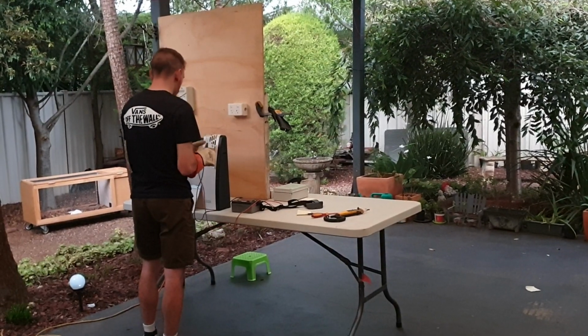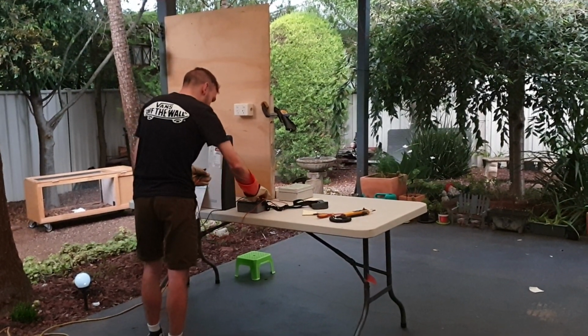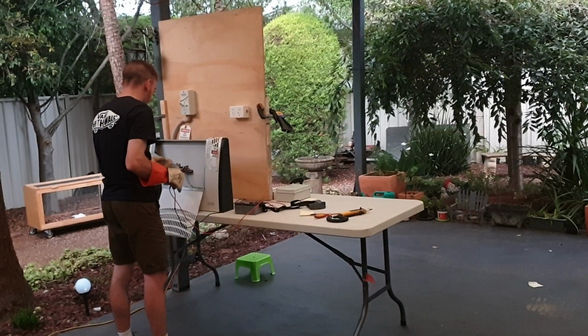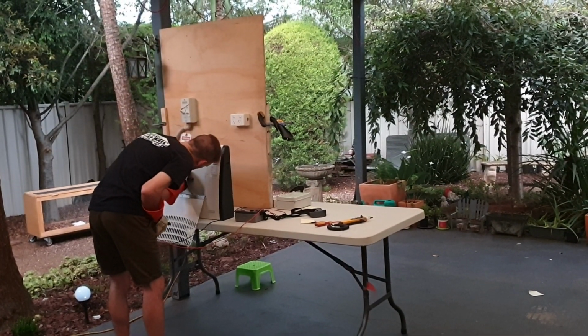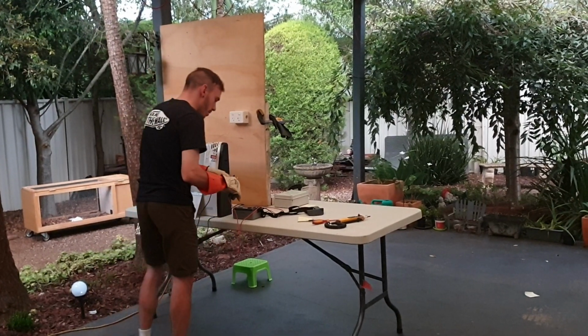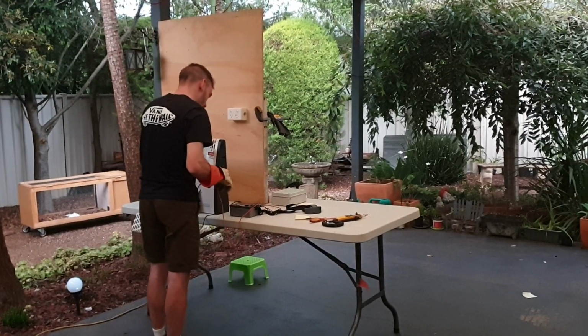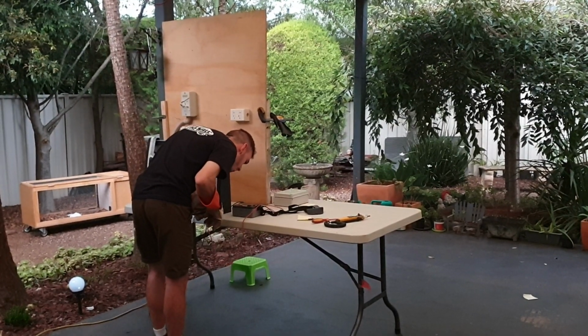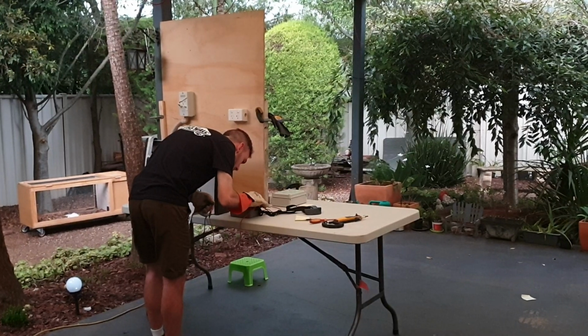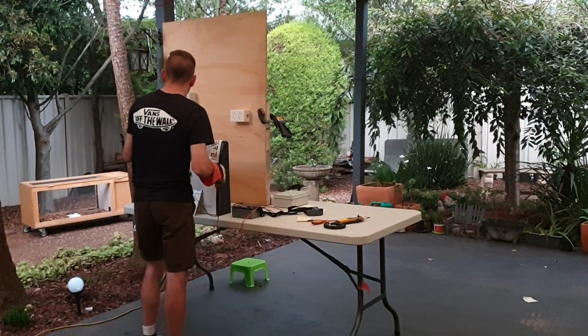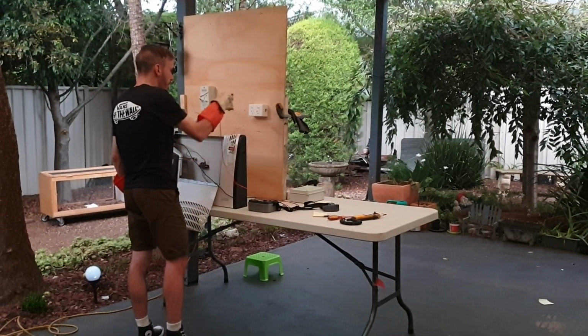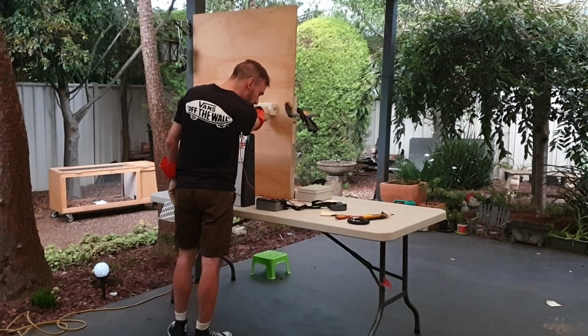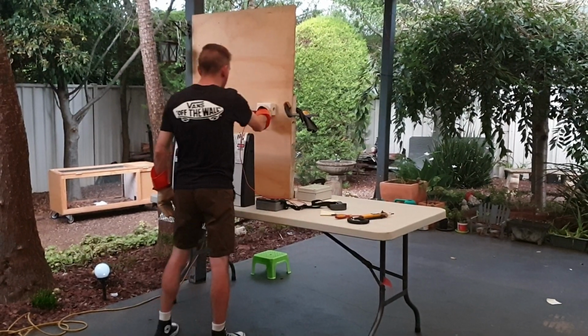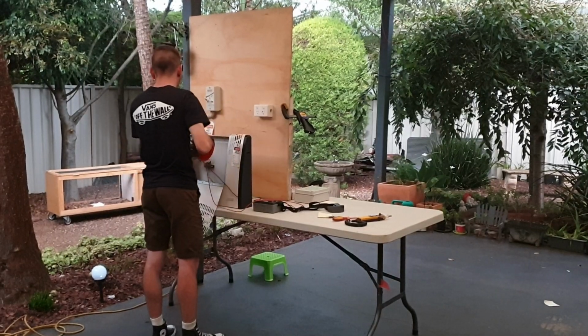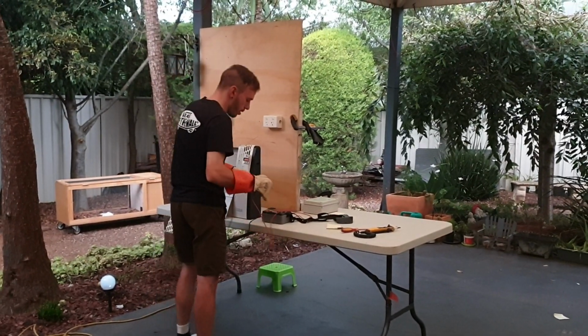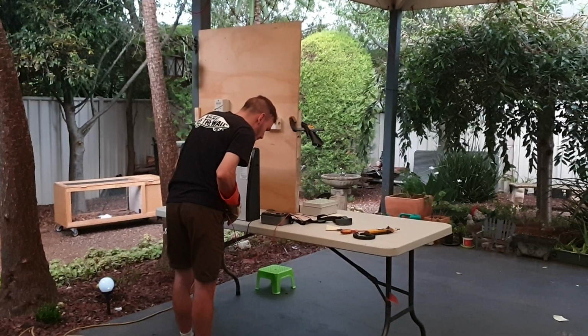It's fine. But before we do the next test, we'll set that to the 3 ohm scale. Install only the earth conductor. Zero at the meter. One more time. Again from the frame to the known earth. Again, that is 0.6 of an ohm, which is a fail. Going to test the meter one more time and zero it.